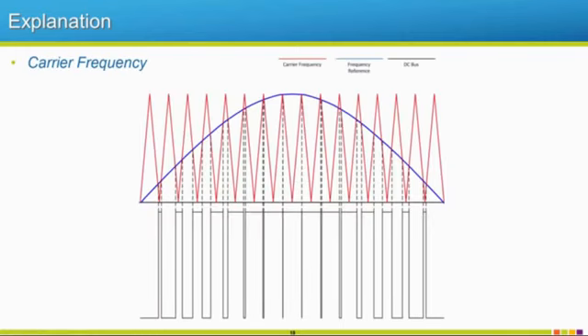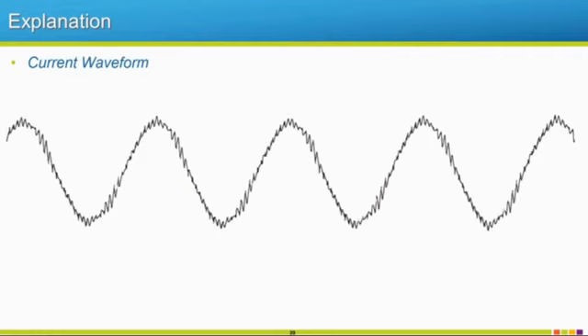You can't really talk about pulse width modulation and not talk about carrier frequency. We talked about it before. IGBTs have a carrier frequency of usually they can be less than two kilohertz, but two kilohertz all the way up to 15 kilohertz. This carrier frequency is inputted into this voltage waveform as a triangle wave. And we use whatever frequency reference we want. So if this is 60 hertz, so how we vary the frequency, this wave that we're trying to make is just going to get squished or wider.